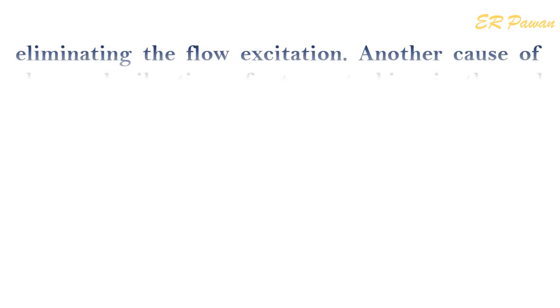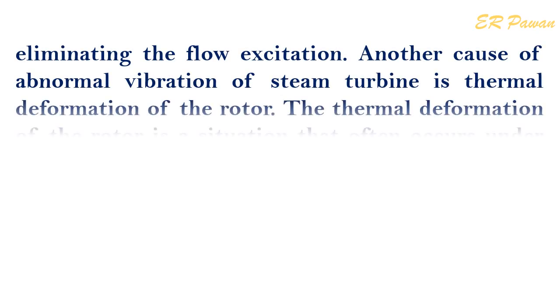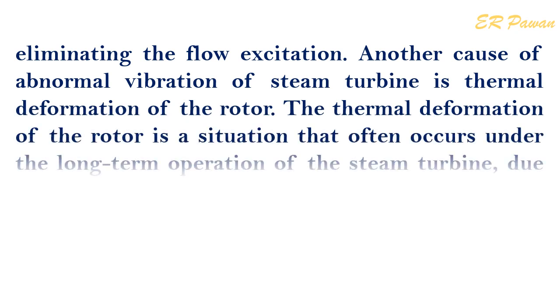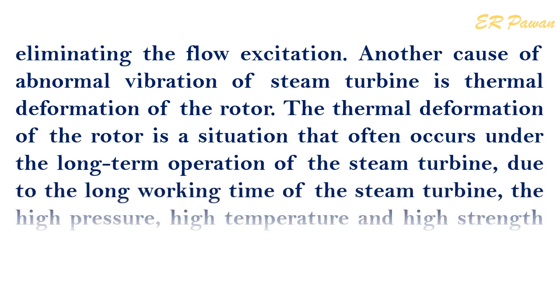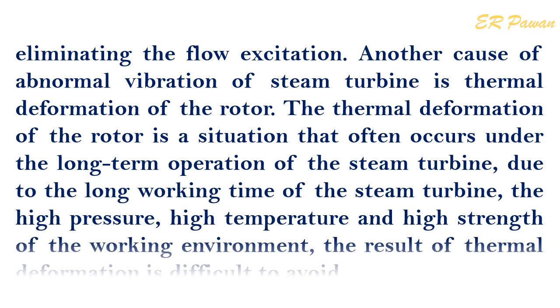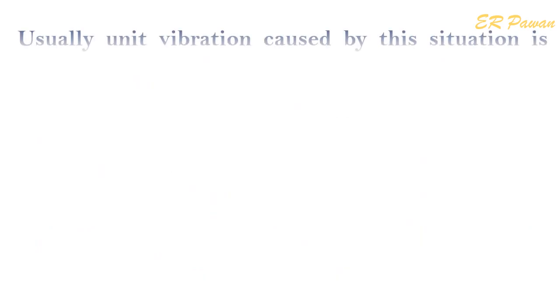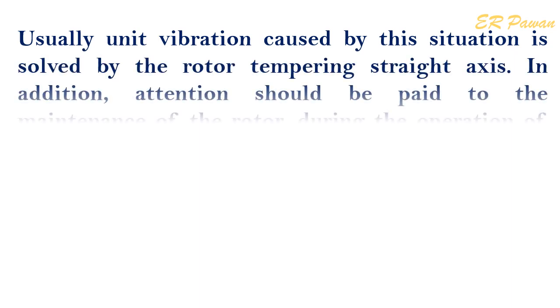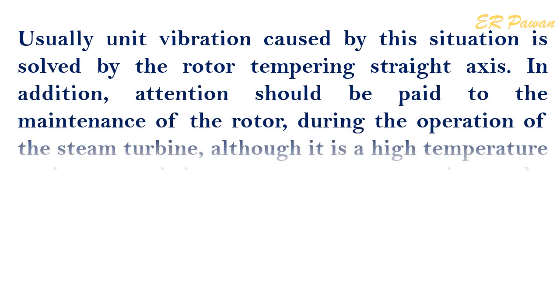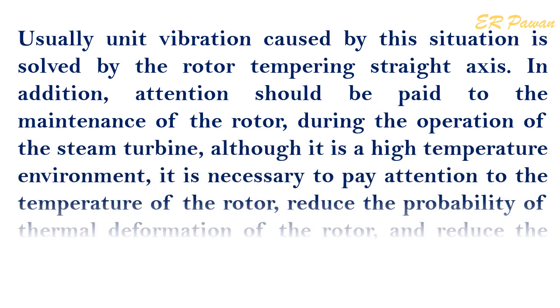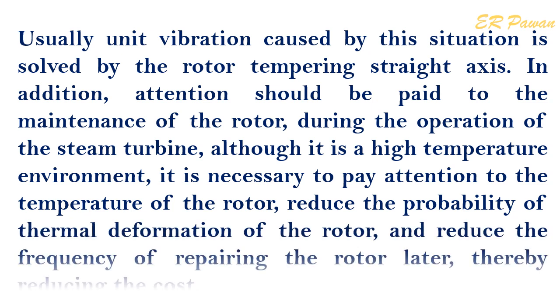Another cause of abnormal vibration is thermal deformation of the rotor, which often occurs under long-term operation due to high pressure, high temperature, and high-strength working environments, making the result of thermal deformation difficult to avoid. Usually, unit vibration caused by this situation is solved by rotor tempering and straight axis correction. In addition, attention should be paid to the maintenance of the rotor during operation to monitor temperature, reduce the probability of thermal deformation, and reduce the frequency and cost of repairing the rotor.